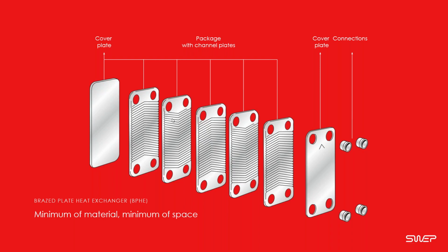This is actually providing some resistance within the channel plates, and that's what allows us to manage and manipulate the heat transfer. So we can change the angle of these chevrons here and the shape of them, depending upon the application. Does it need high resistance, or if pressure drops are a concern, do we need to look at low resistance as well? These are built automatically. These plates are stacked together in the factory on the production line.